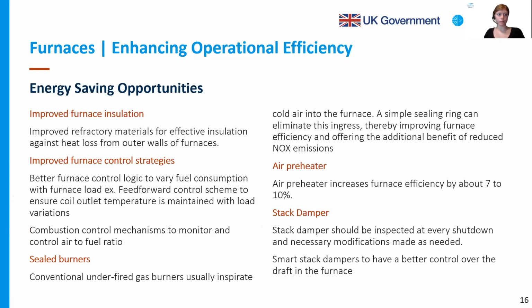So as with boilers, furnaces, ovens, or any thermal energy systems, I would like to stress that there are three main aspects of consideration for efficiency, not something we don't know. It's basically heat generation, heat containment, and heat transfer. How efficiently are you generating thermal energy? How effectively are you containing this energy, minimizing loss to the environment, and how effectively is this energy transferred to your heating load? So if we can ensure that all these three aspects are sealed, that's when you're driving maximum efficiency in your thermal energy management system. So the holy trinity: generation, containment, and heat transfer.